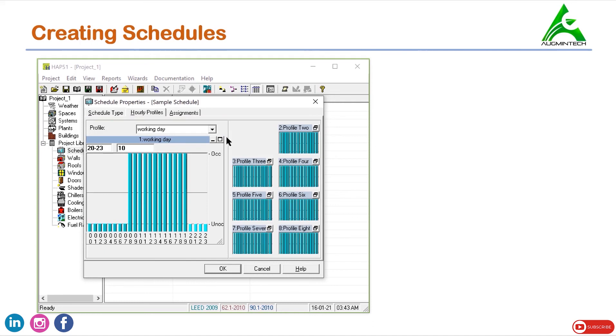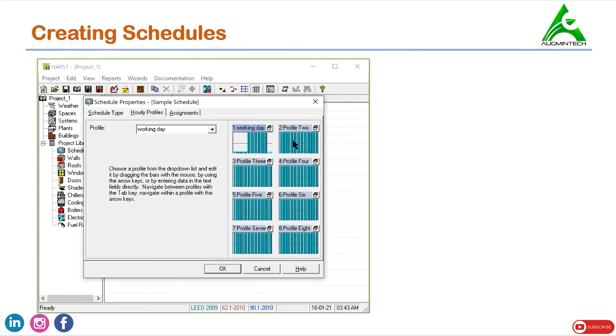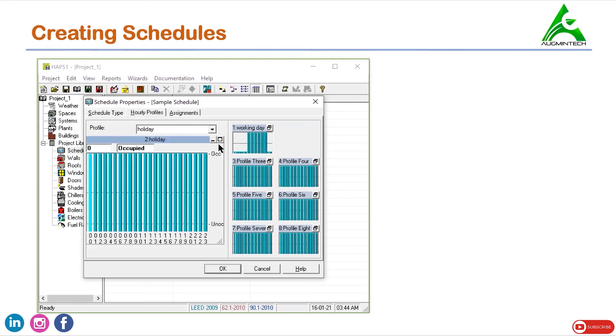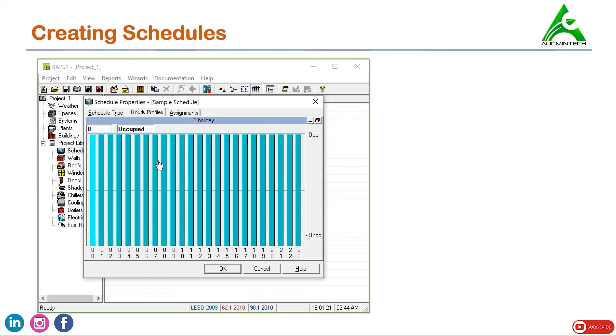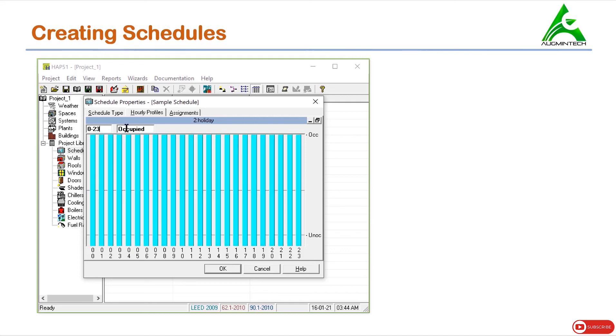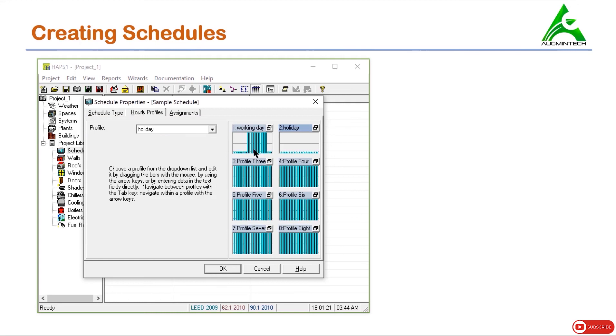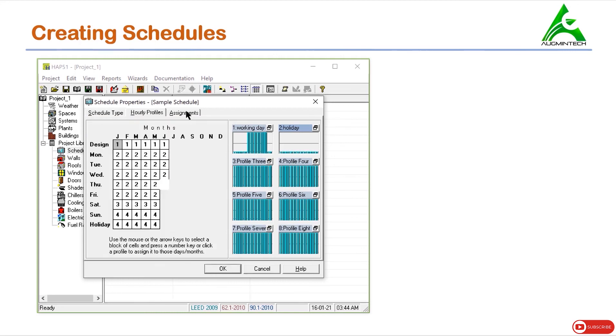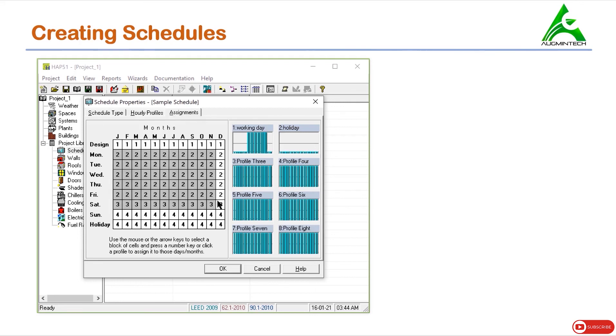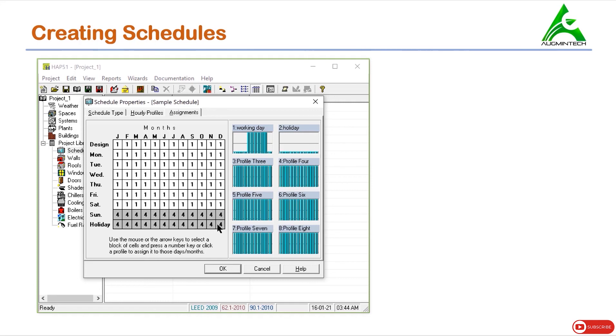We'll minimize the working day profile and define another profile for holiday. On a holiday, the office remains closed with no work being done, so for all hours (0 to 23) we set the value to unoccupied. We'll minimize this. Now we have defined two different profiles for the fan. In the assignment tab, from Monday till Saturday we select the working day profile, and for the remaining days we select the holiday profile. We have now assigned the fan profile for each day throughout the year. Let's click OK and proceed.